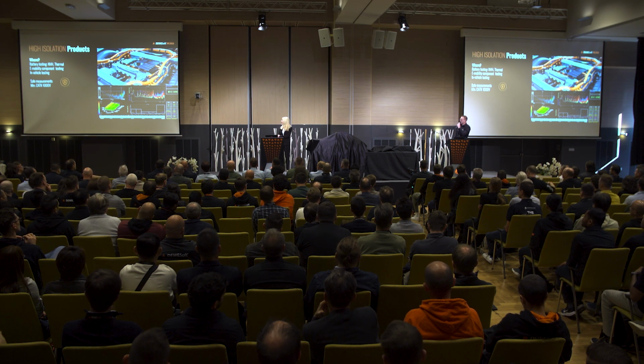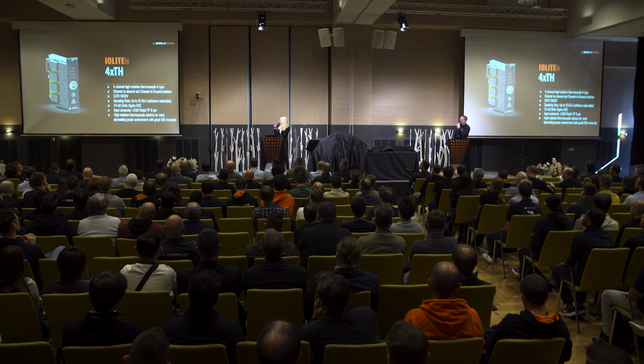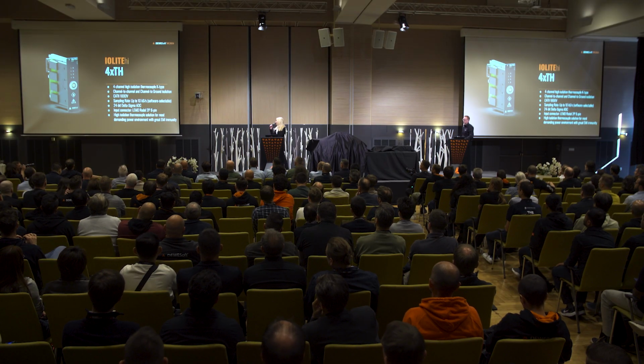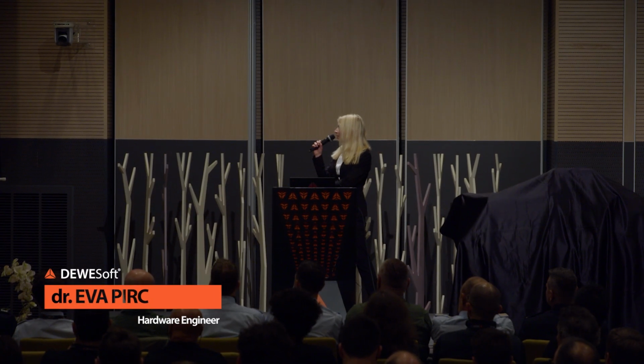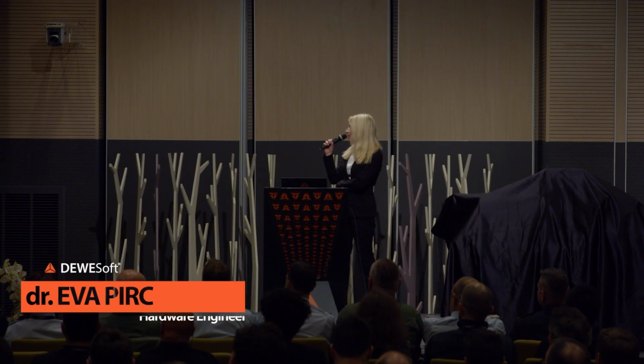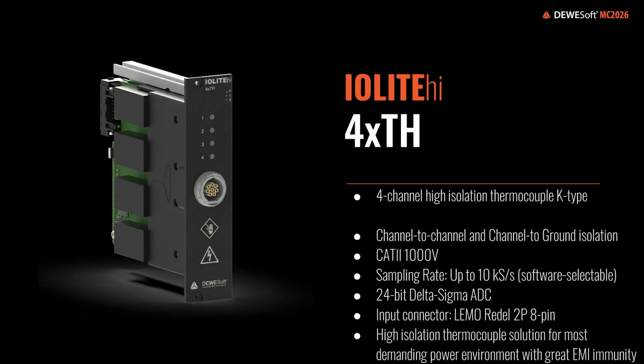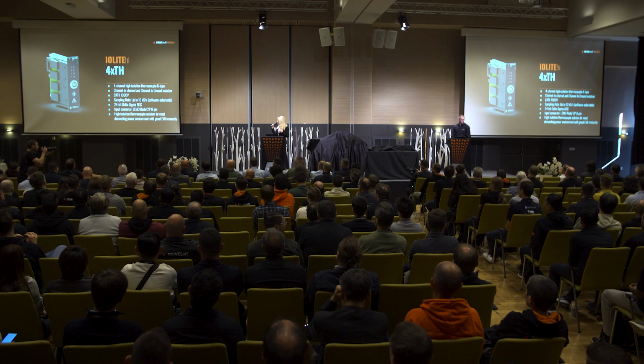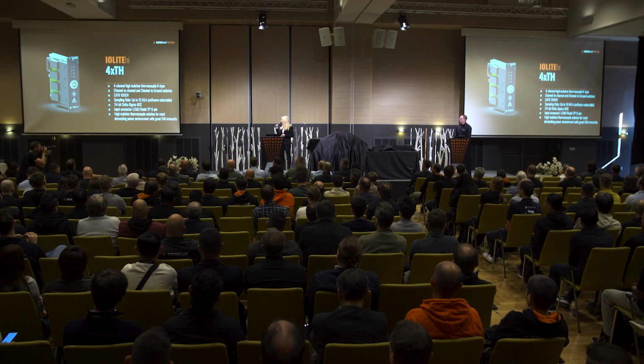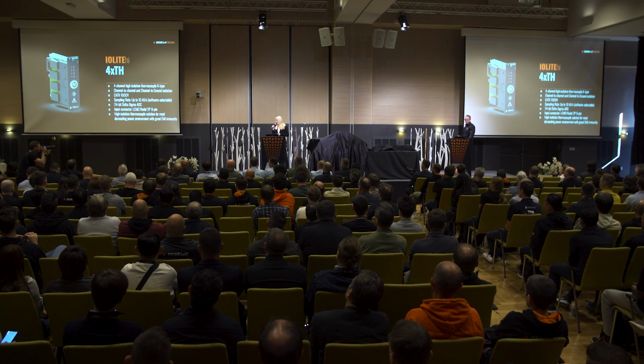Eva, can you please explain which are these products? Yeah, so the first product is called IOLITE, high isolation, 4 times thermocouple. And as the name says, it's a 4-channel, fully isolated K-type thermocouple module. It's channel to channel and also channel to ground isolated, Cat2 1000 volt rating. It's perfectly suited for the harsh power environment, ensuring a great EMI immunity.